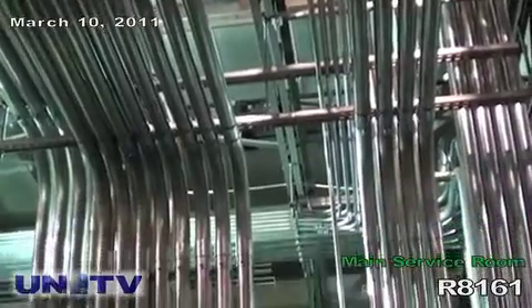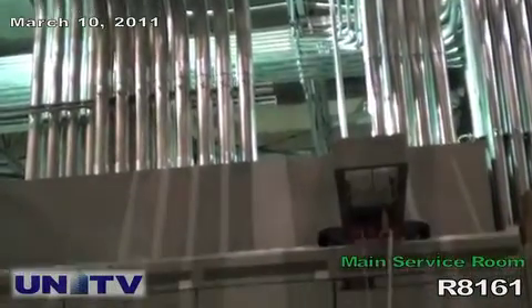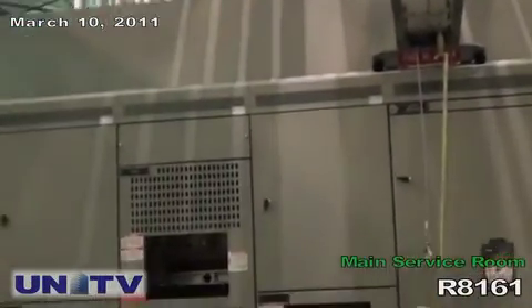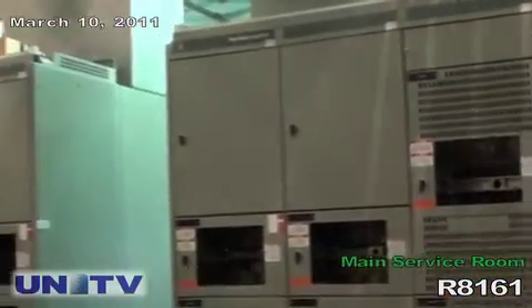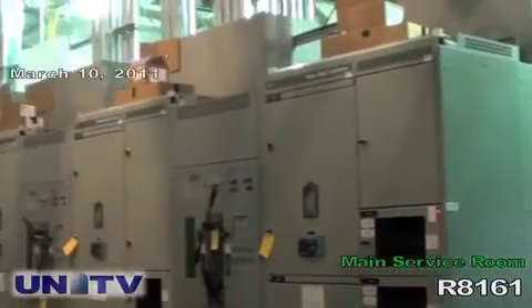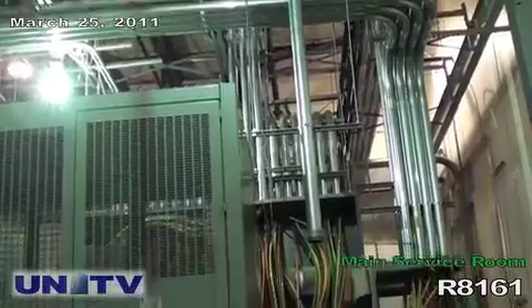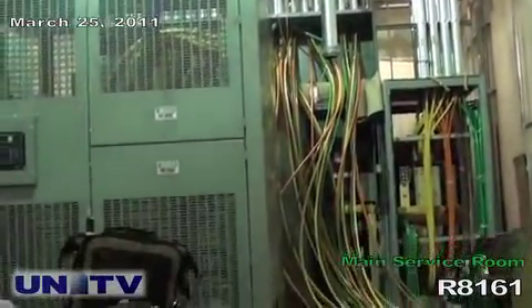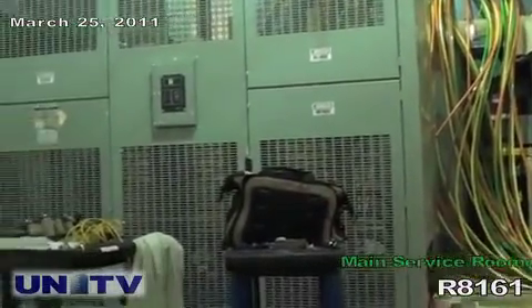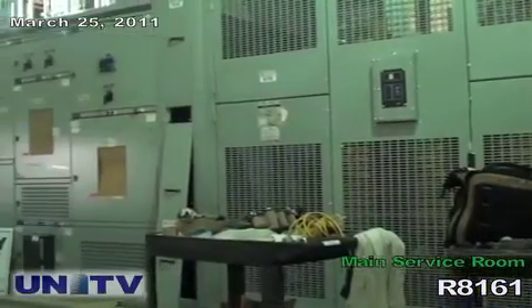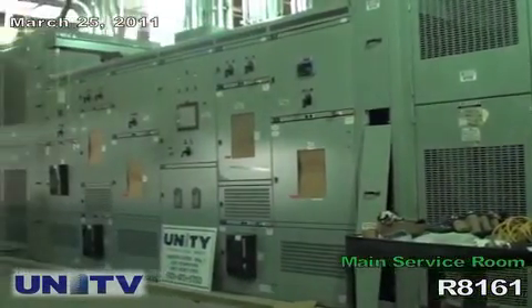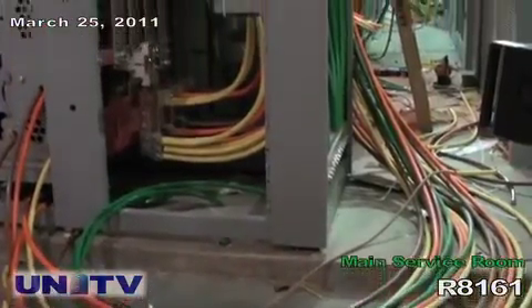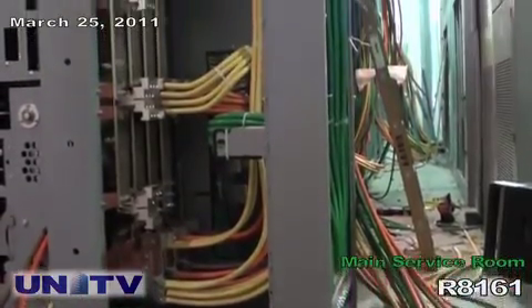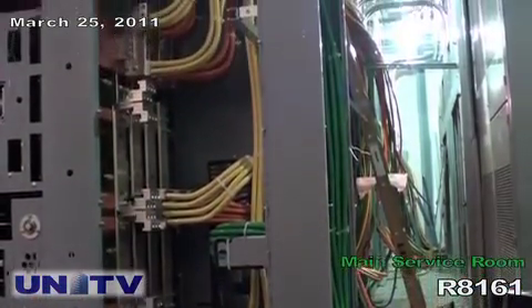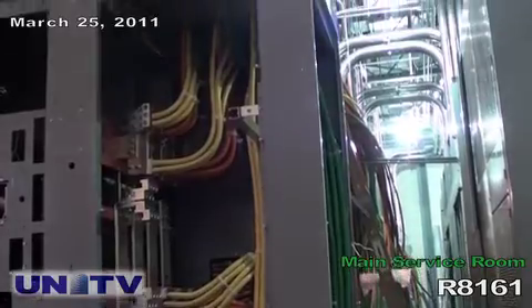What you're looking at here is a switchboard. It's 480 volt, 3-phase, and the distribution panels. Here is your service coming in. It's a 13.2. You have the ability of bringing redundant feeds in, and in the middle is a tiebreaker, which gives you the availability of using one service or the other in case there's a power failure.